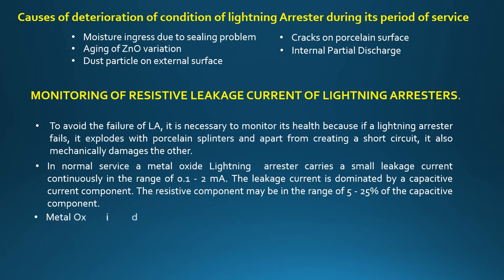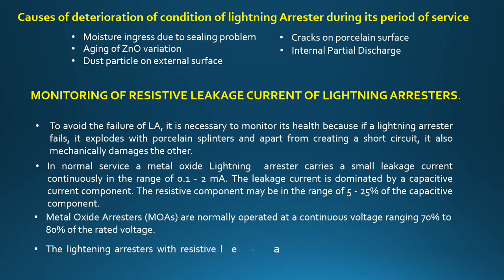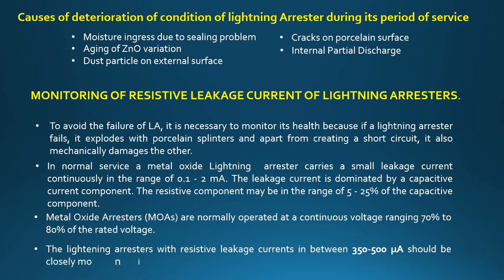Metal oxide arresters are normally operated at a continuous voltage ranging from 70 to 80 percent of rated voltage. Lightning arresters with resistive leakage currents between 350 to 500 microampere should be closely monitored, and those beyond 500 microampere should be replaced after due testing.